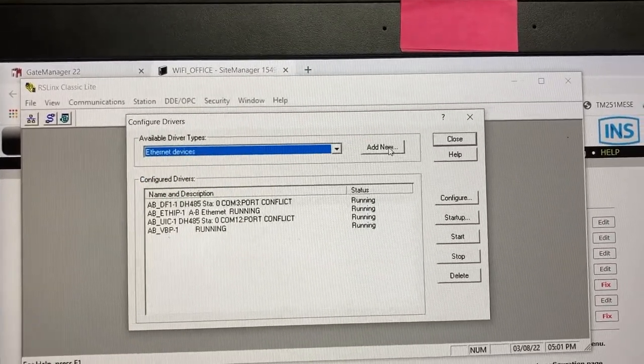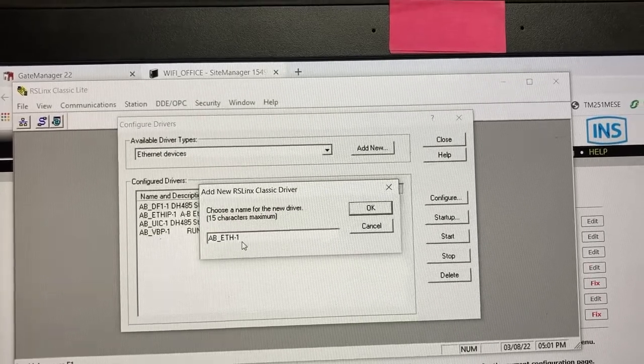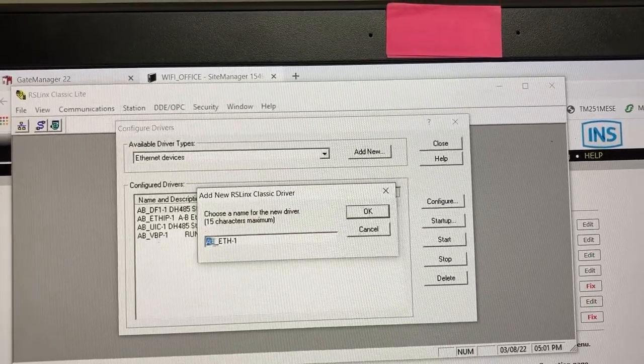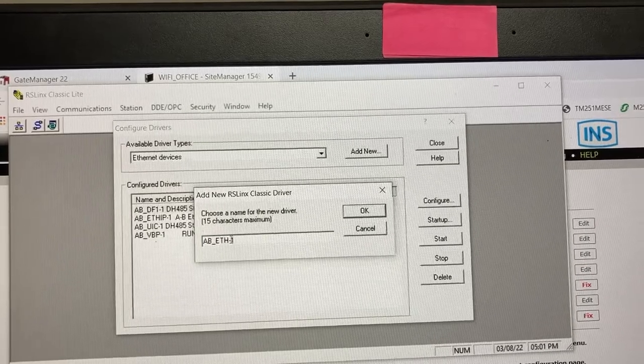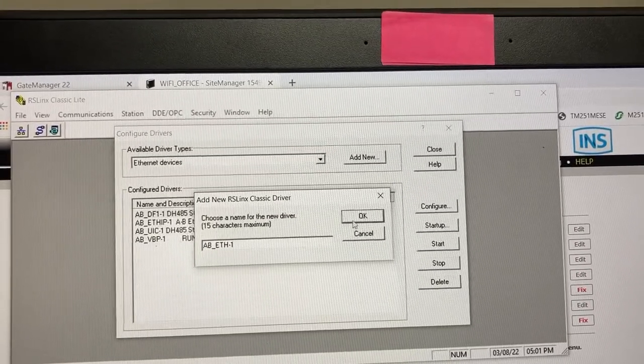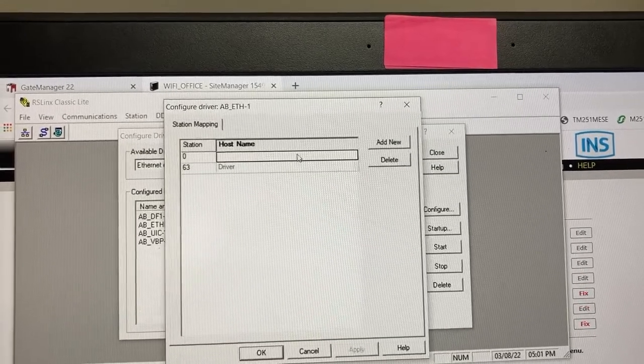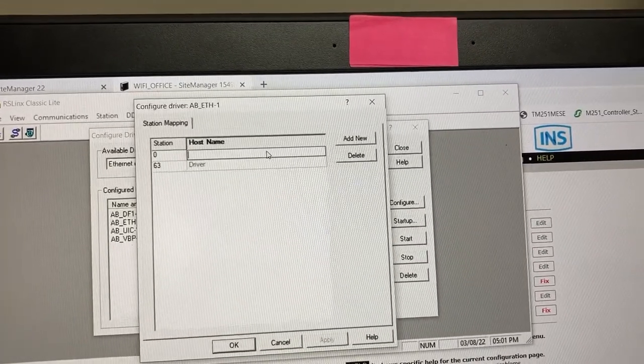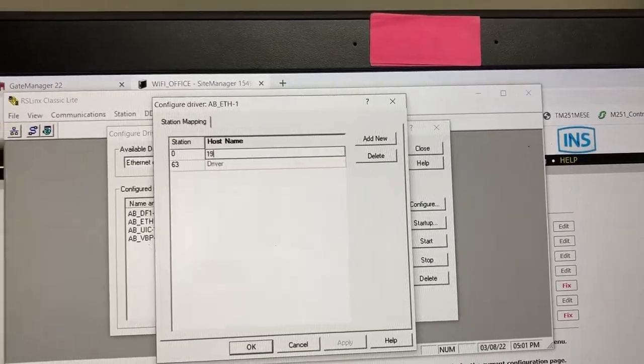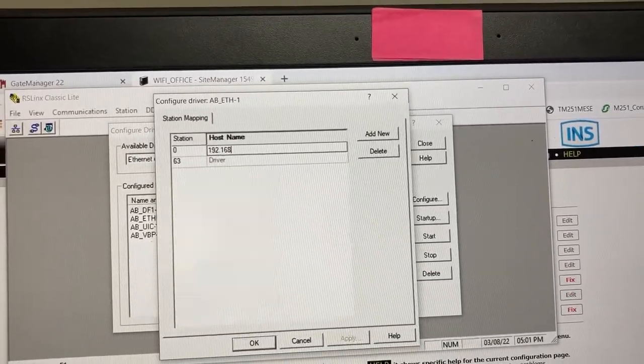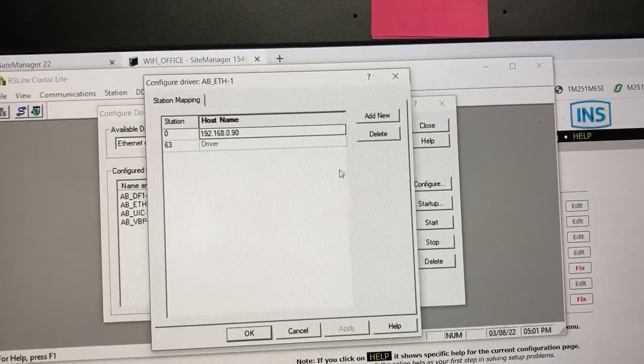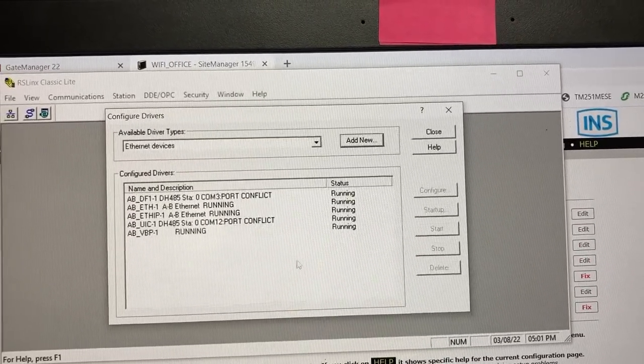Select Ethernet Devices. Add New. Name it, it will be AB_eth-1. OK. Type in the PLC IP address 192.168.0.90. OK. Close.